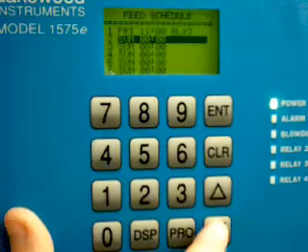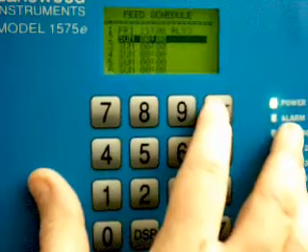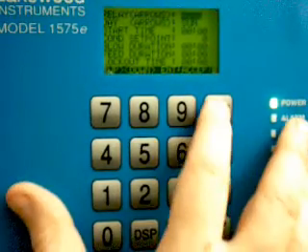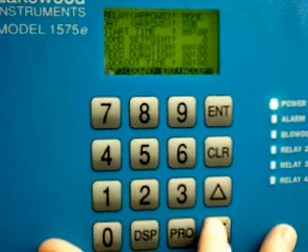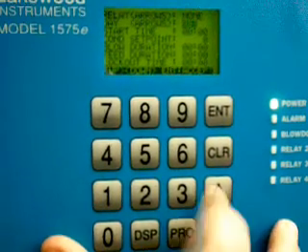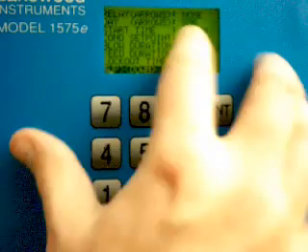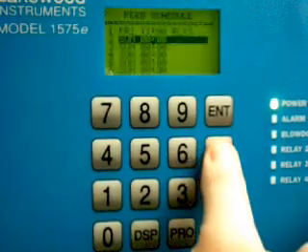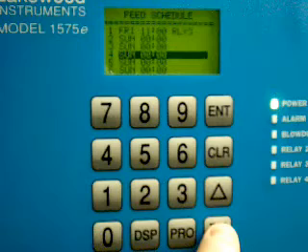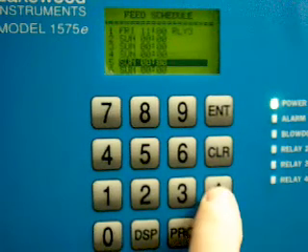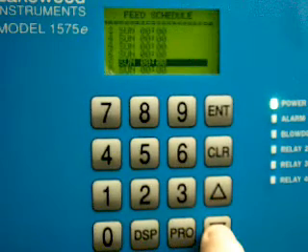Now, if I wanted to feed the same chemical on Thursday or Tuesday, I'd go down to the next step in the chemical feed schedule, hit enter, I'd go ahead and use relay 3, and then for my day, I'd pick Thursday or Tuesday. So now it's Tuesday, and I would finish the rest of my steps. So I can have multiple days. Each line of that feed schedule allows me to enter a new time and date, a new set point, all those parameters. And I can have, let's see here, we've got, I think, 15 or 20 of these actual steps that you can go through to have the chemical feed at various times and dates.